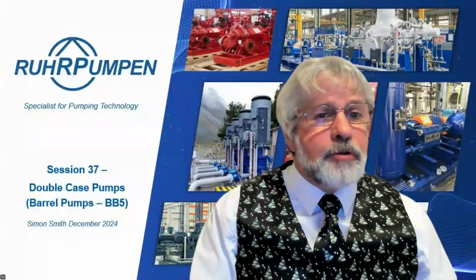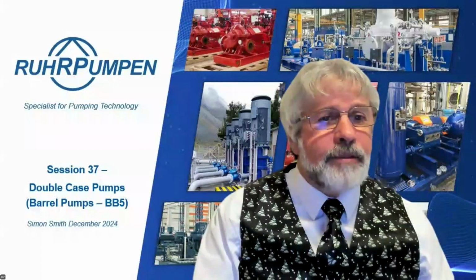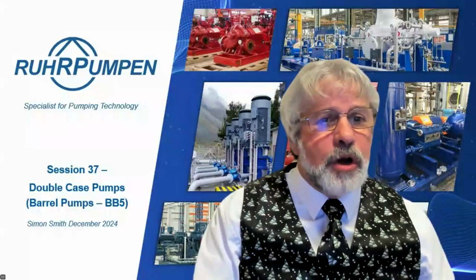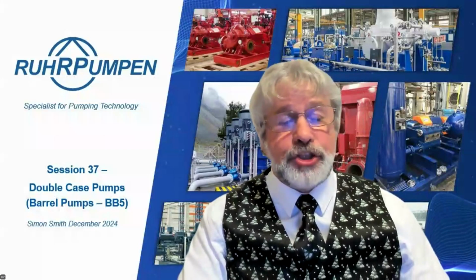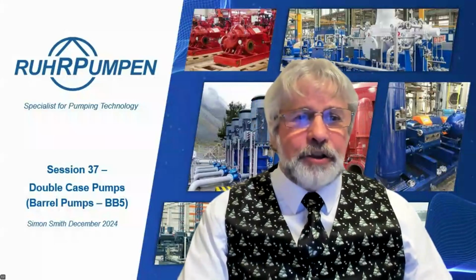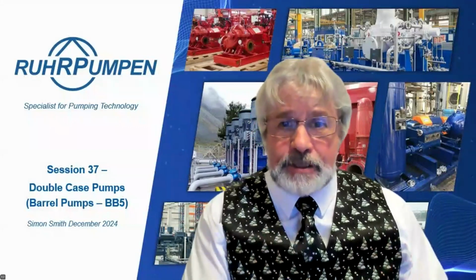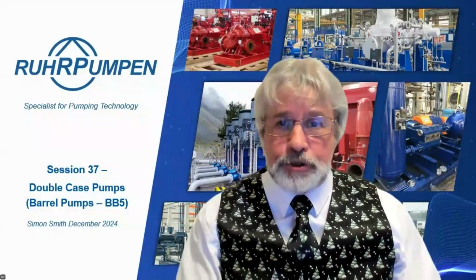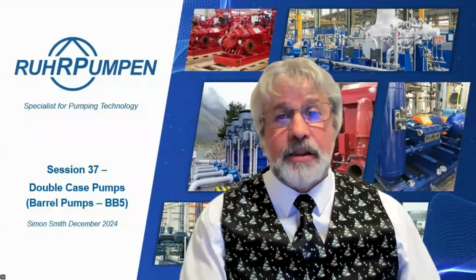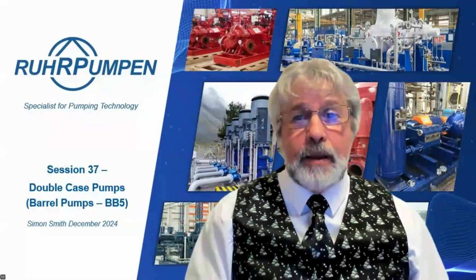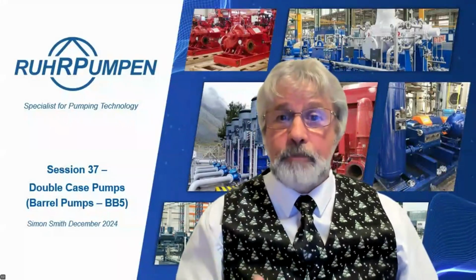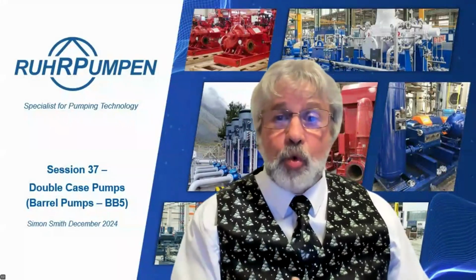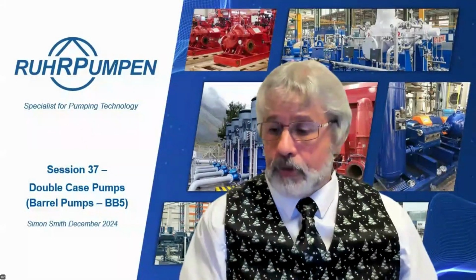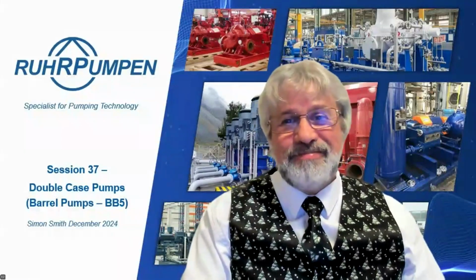Victor Mihangos says there are two types of balancing thrust devices, the thrust drum and the disc. Would you please explain how each of these work and how is the balance calculated and or managed? Can't do that easily. First, let's say the first thing. There's a thrust disc and a thrust drum. API 610 only allows you to have a thrust drum. It won't allow you to have a thrust disc. Thrust disc is often used in BB4 pumps that are on clean applications such as water injection or power station use. Yeah, boiler feed. That's what I'm looking for. Boiler feed pumps can use them. Clean pumpage.